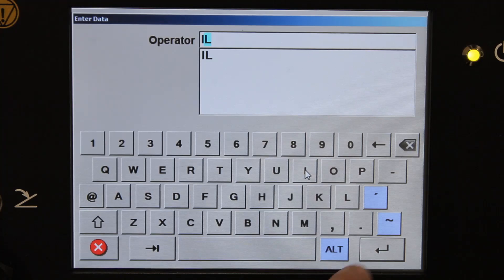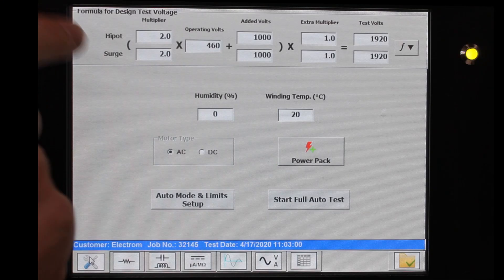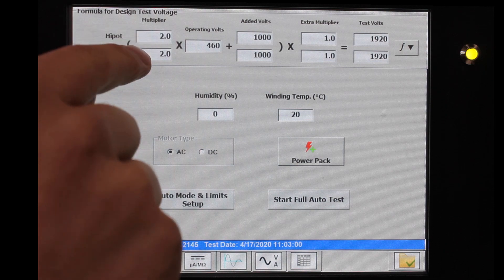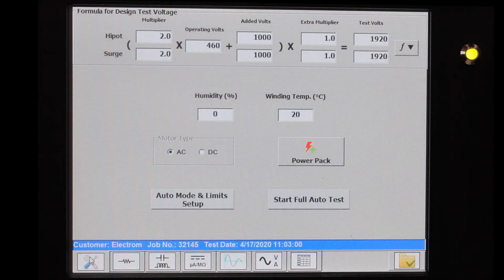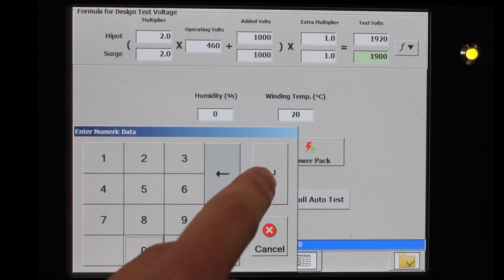Enter operator information. Next step, go to the setup screen. We have our Hipot and Surge test voltage formulas. The test stage we selected defines it to 2 times the operating voltage plus 1000. If you don't like the final test voltage, you can click the white field and enter in your preferred test voltage.